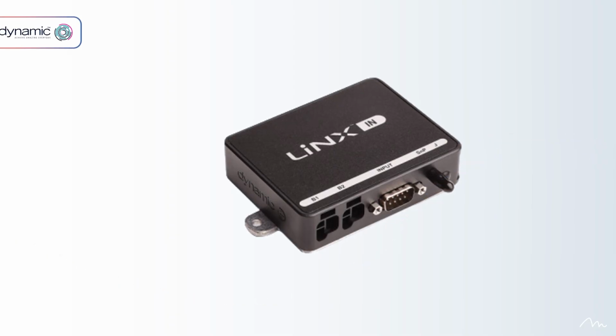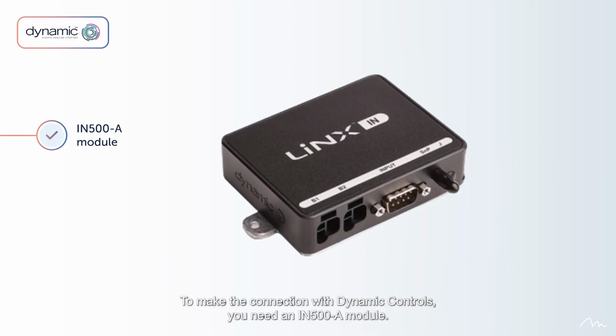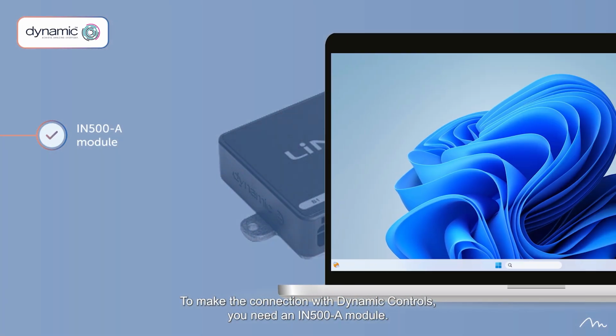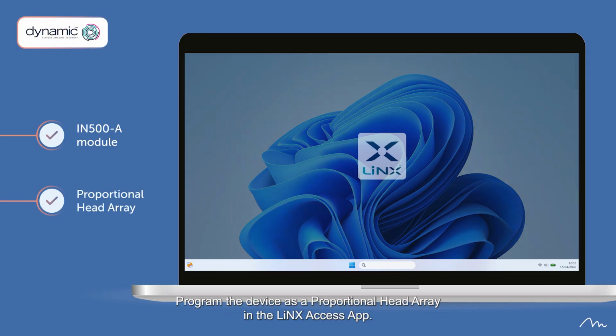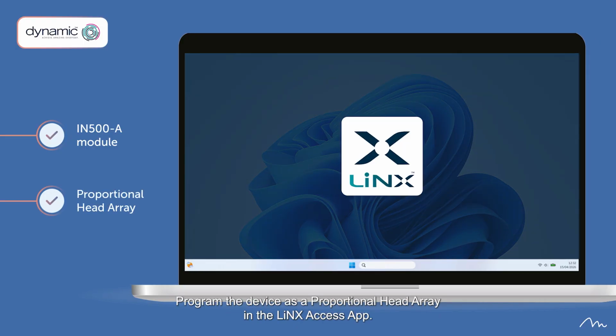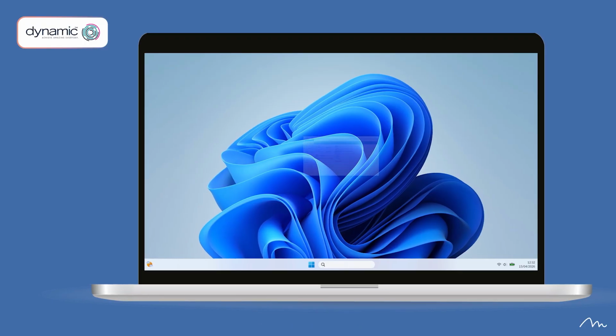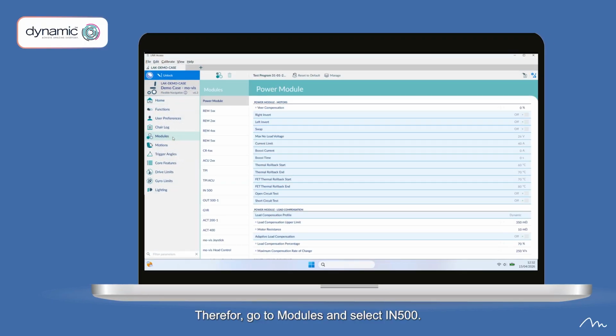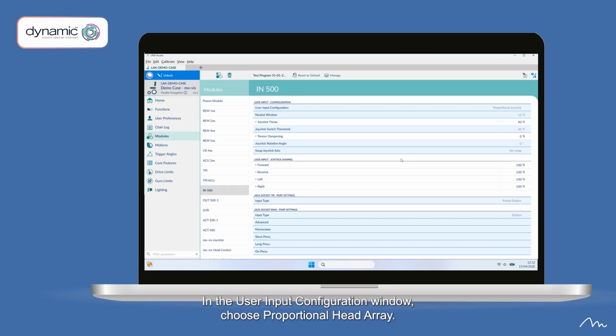To make the connection with dynamic controls, you need an IN500A module. Program the device as a proportional head array in the LiNX Access app. Therefore, go to Modules and select IN500. In the User Input Configuration window, choose Proportional Head Array.